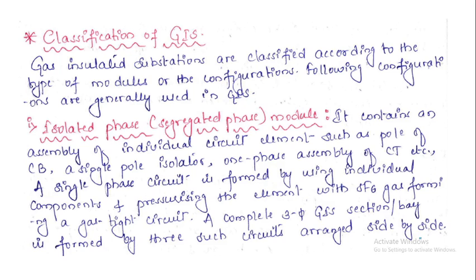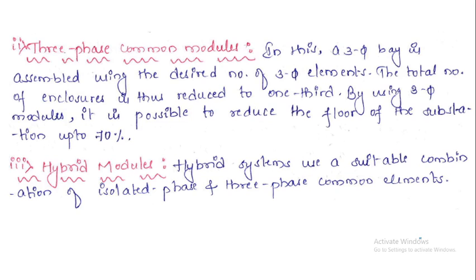So by taking the individual components, we make one unit with the help of pressurized SF6 gas. In order to make a three-phase circuit, we take three such units side by side. So that is the first, isolated phase. Next we have the three-phase common module. In this, a three-phase bay is assembled using the desired number of three-phase elements. The total number of enclosures is thus reduced to 1/3.